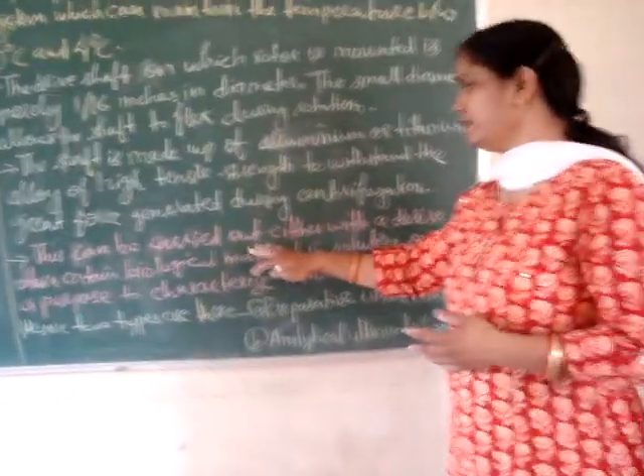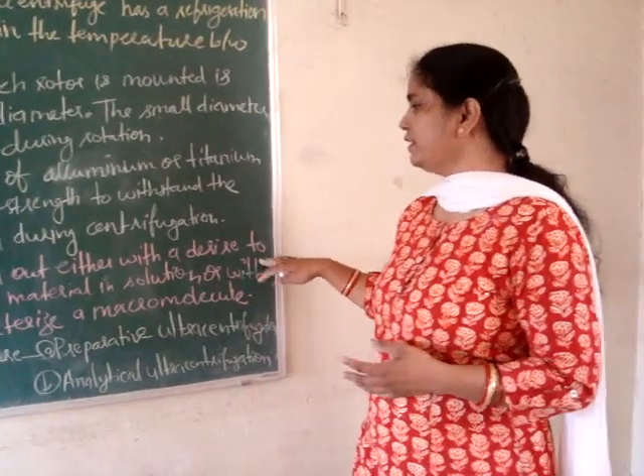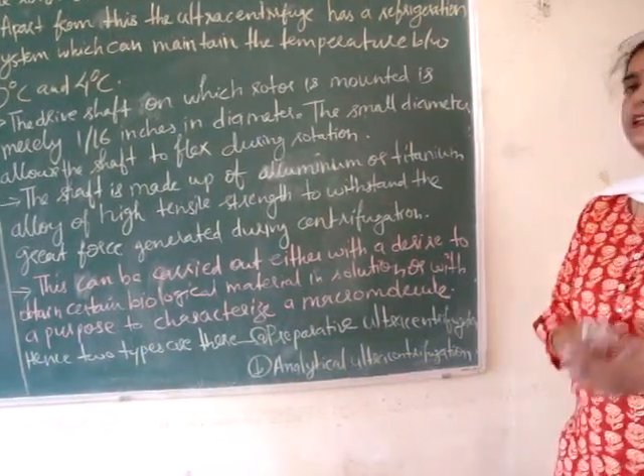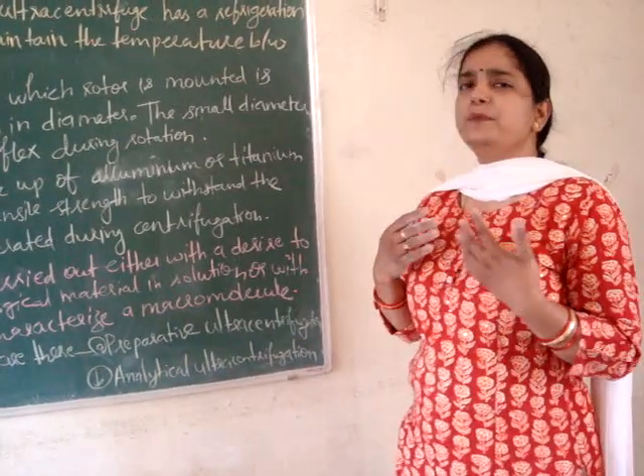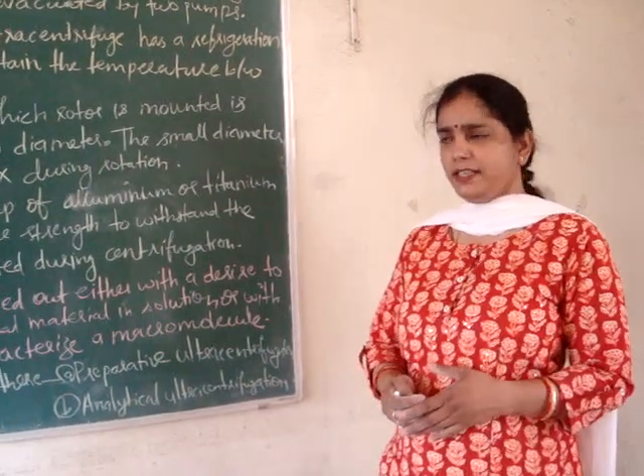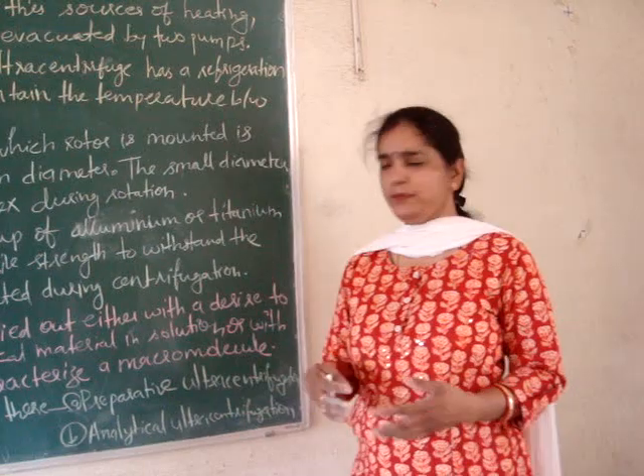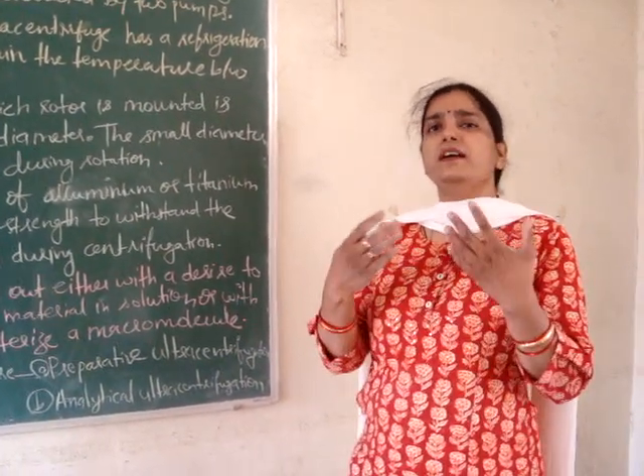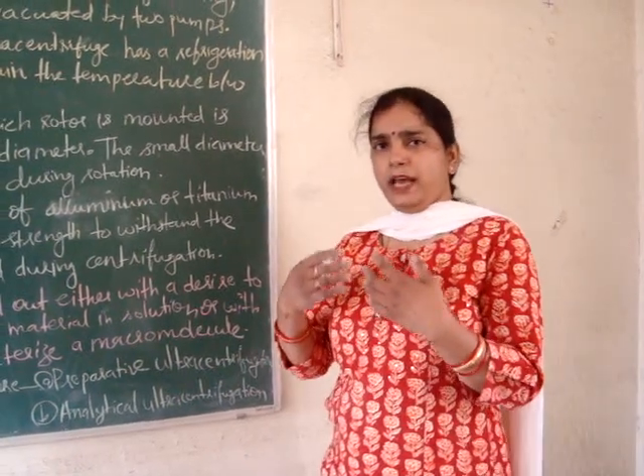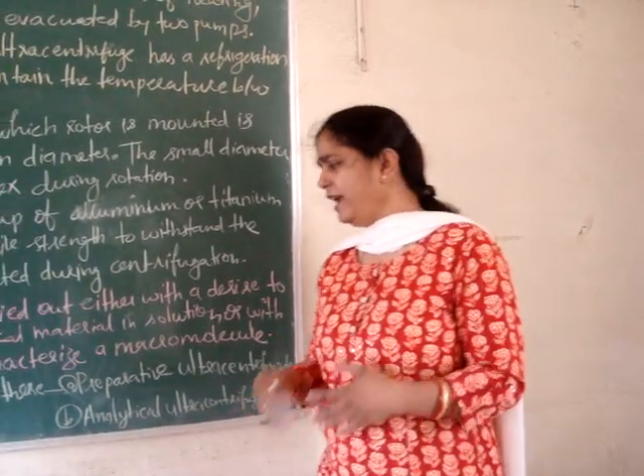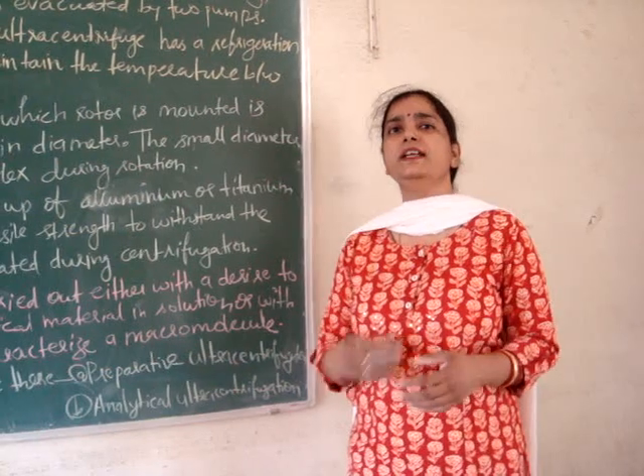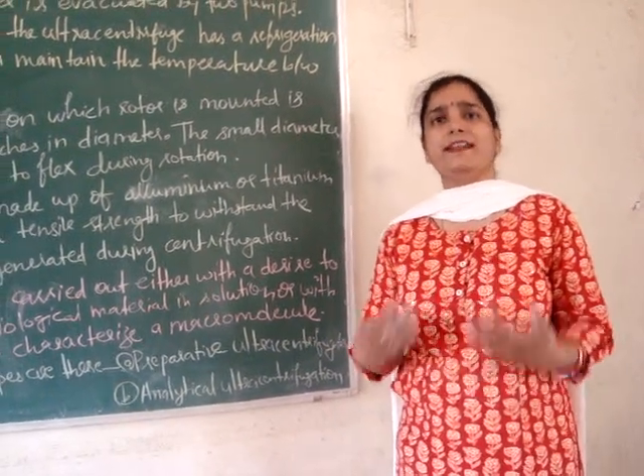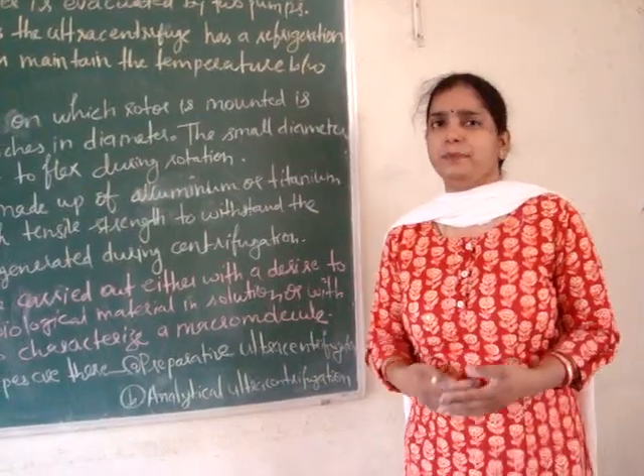Ultra centrifugation can be carried out either to obtain a certain biological material in solution, or to characterize the biological material. Hence, there are two types of ultra centrifuge: the preparative ultra centrifuge, used to isolate a biological or any sample; and the analytical ultra centrifuge, which is used not only for isolation or separation but also to characterize the particular sample.